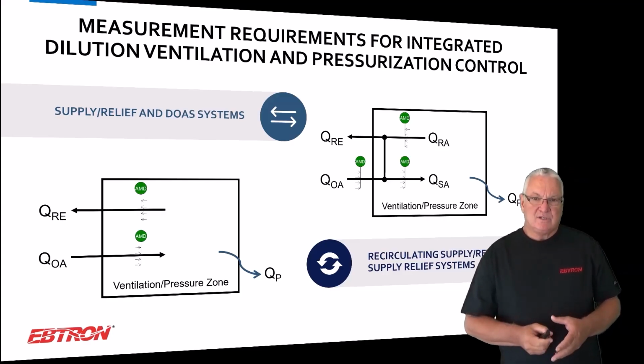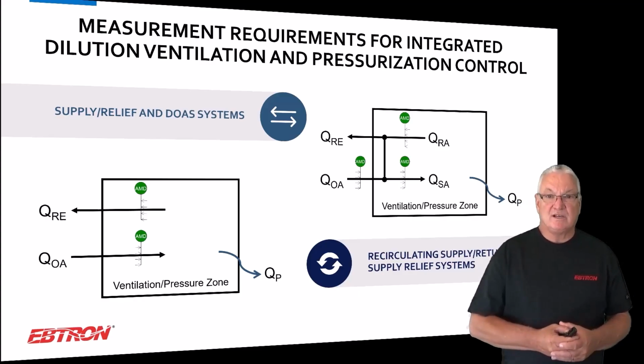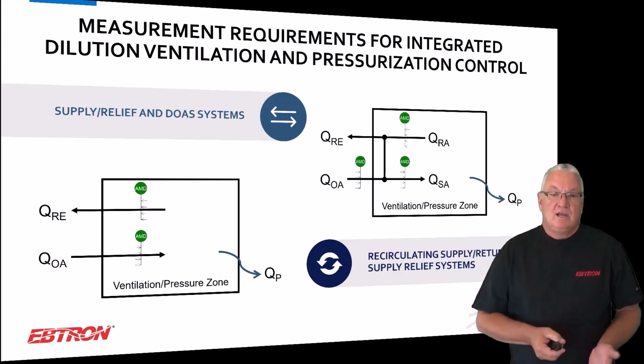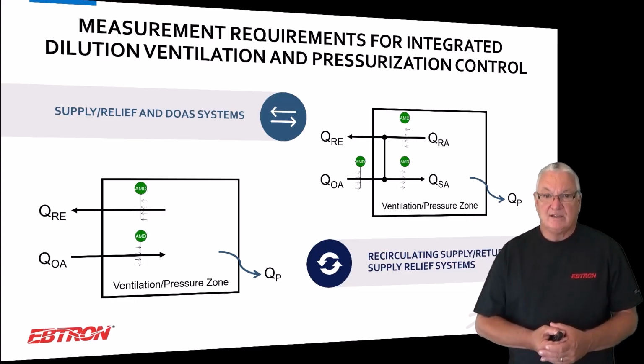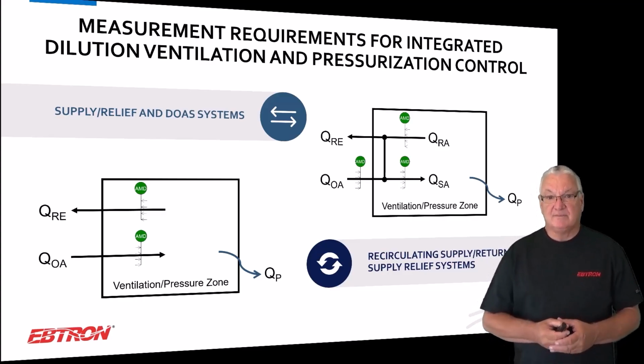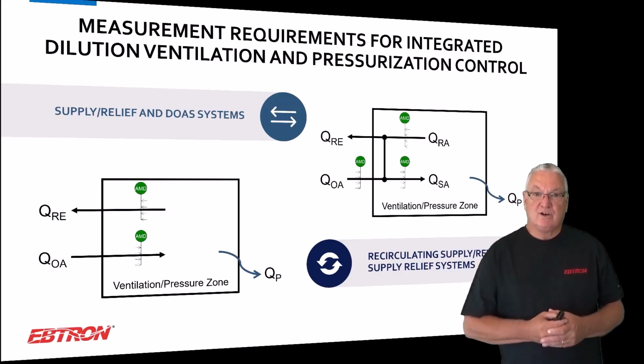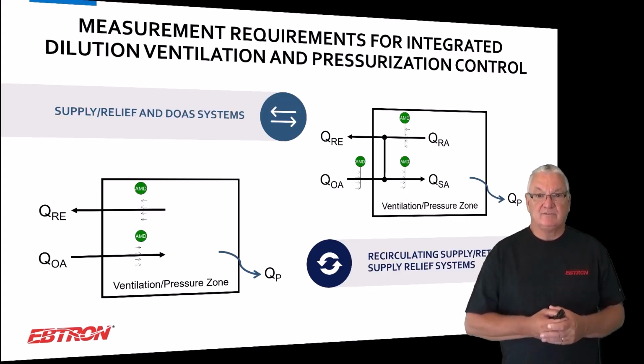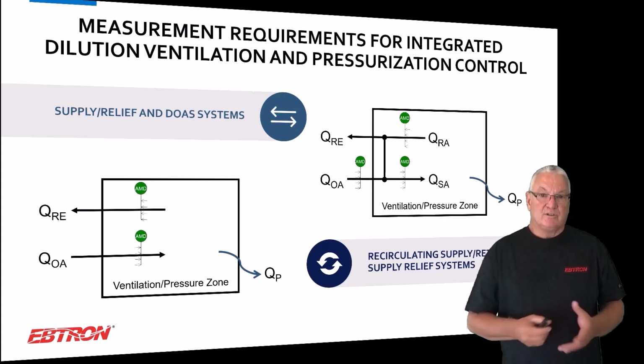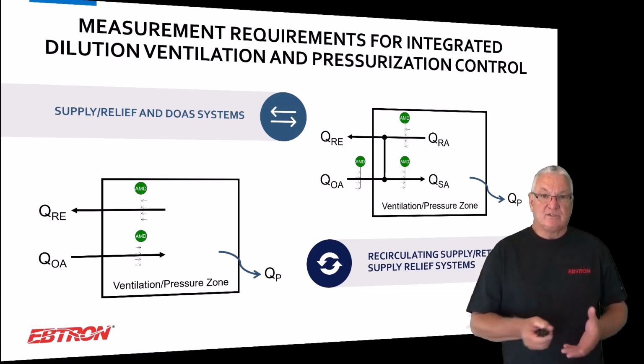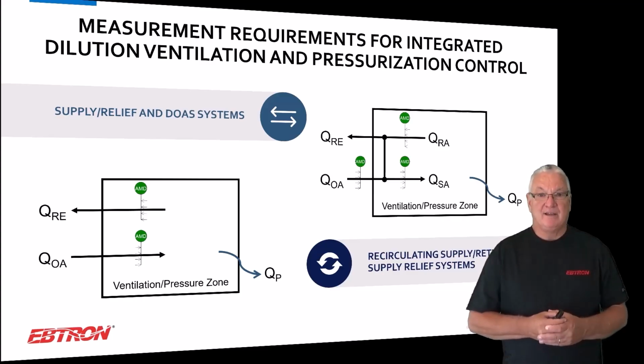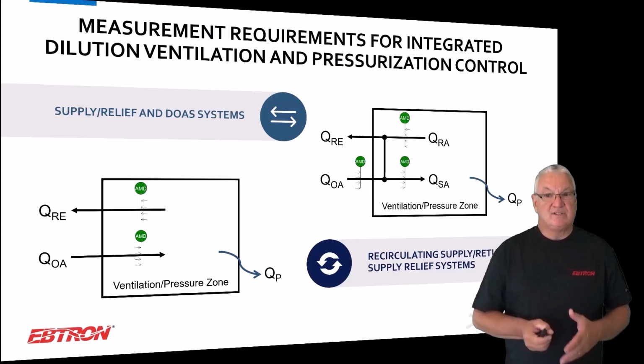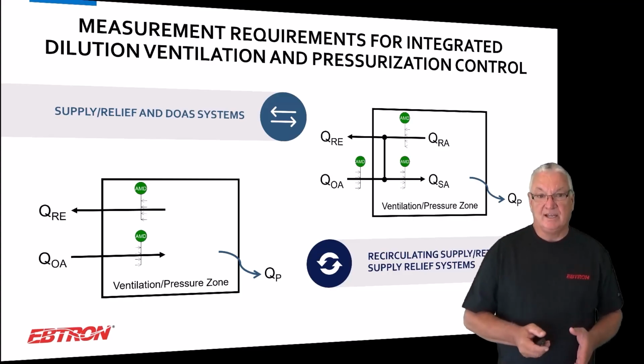Recirculating air systems. Recirculating air handlers are pretty straightforward too, but not everybody always does what's obvious to me. Okay, so in the case of a recirculating air handling system, we're going to control our pressurization flow by the difference between the supply and the return air flow rates, and we're going to maintain our outdoor air for dilution with an outdoor airflow station. Okay, we're not going to measure the relief. We're not going to measure the recirculation path. These are the three measurement points that we need. I've seen people do everything. This is all you need, okay?